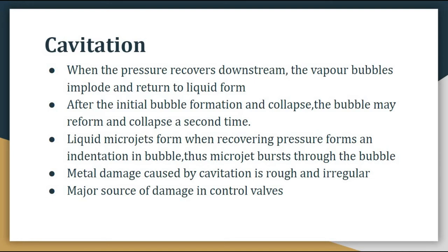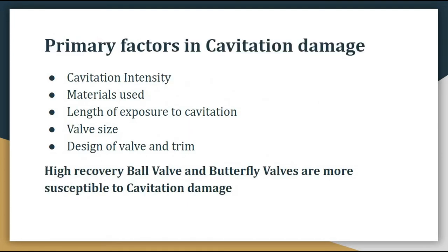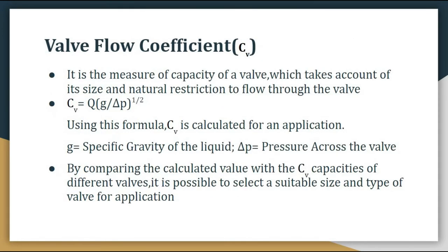This creates a very undesirable condition, and cavitation is the major source of damage in control valves. The primary factors in cavitation damage are: cavitation intensity, the materials used, length of exposure to cavitation, valve size, and design of valve and trim. The control valves most susceptible to cavitation damage are high recovery ball valves and butterfly valves.